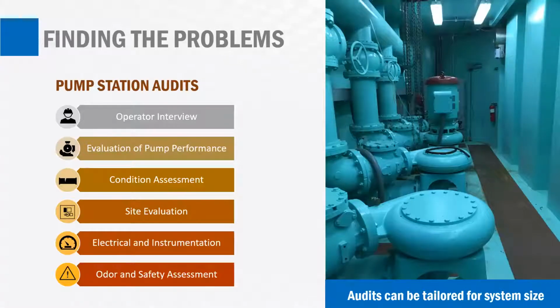Condition assessment. There's different materials at your pump station sites, between pipes and structures and panel boxes and so forth. What's the overall condition of those materials? Site evaluation. When you go out to the site, can it be easily accessed? Are there other site issues? Flooding that might occur out on site. Electrical and instrumentation. It's important to not forget about electrical and instrumentation. With electrical, are arc flash considerations considered? With instrumentation, are your floats working properly? Other systems with instrumentation, are they working properly? And then with odor and safety assessment, it's important to make sure that O&M staff are safe, that the public health is taken into account, and that any nuisances are also taken into account.